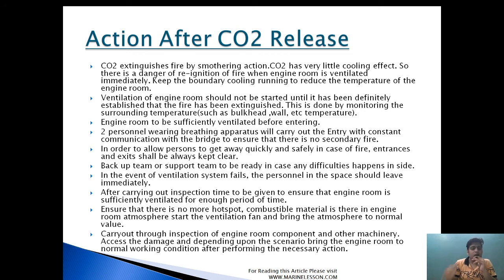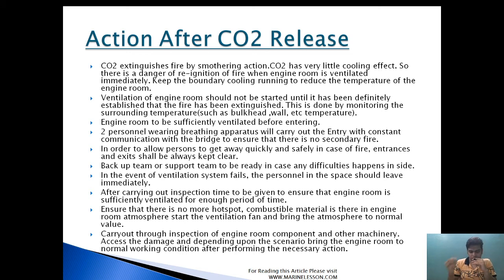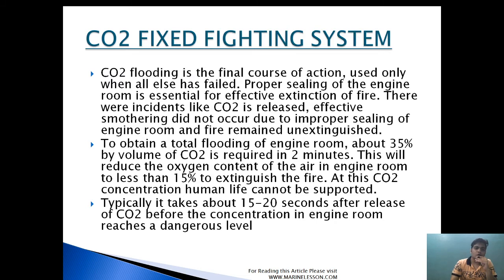When oxygen reads 20.9 percent at all levels and there is no secondary fire, final entry is performed. A thorough inspection of all engine room components and machinery is carried out, damage is assessed, and depending on the scenario, the engine is brought back to normal working condition. After final entry, the generator is started, power is restored, systems are checked, cleaning is performed, crankshaft deflection is checked, and free rotation of the engine is verified.